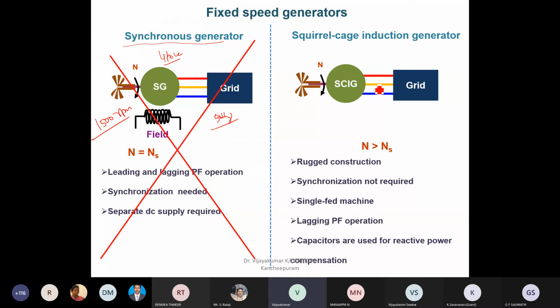So only that's what we can say is a singly fed machine. But if you talk about the synchronous machines, you have the field as well as the armature. So there are two, we can say it's a doubly excited machine. For the field, you need to give DC, and in the armature, you will get AC. So you require two types of power supplies. But here only AC, right? Here only AC. So this is another disadvantage. Then if you talk about synchronous machines, the cost is higher than the squirrel cage machines, right? So because of these three reasons, we will not prefer the synchronous.